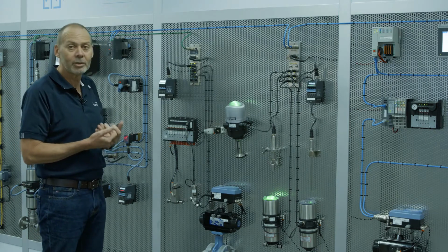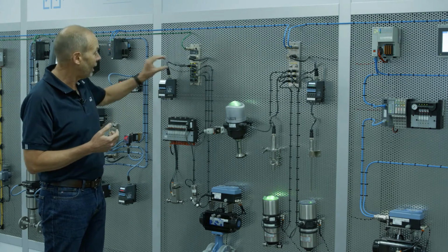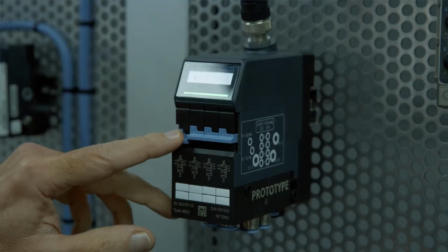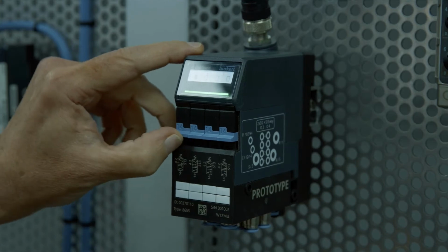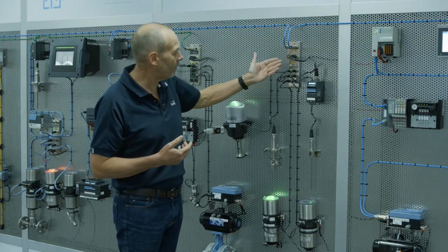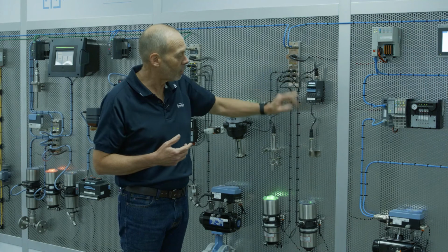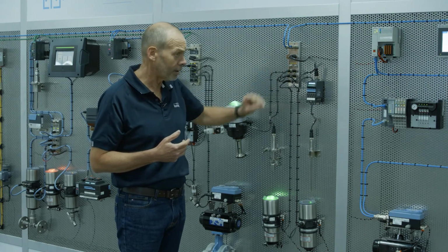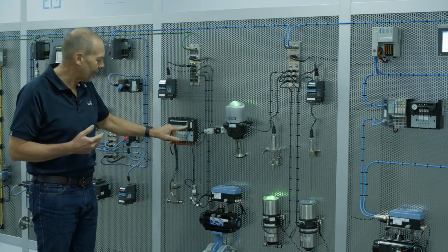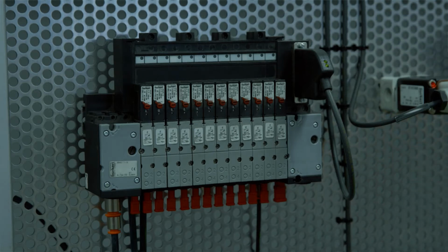However, the ports can also talk digital communications to the devices in the field. A similar IO-Link port in this instance is talking to a block that has 4 valves in there controlling actuators in the field. Alternatively, over here we have a block talking to 8 valves in the field. These valves are all controlled via the IO-Link block. And on that same type of network port, in this example, we have up to 24 valves connected on a single IO-Link port.